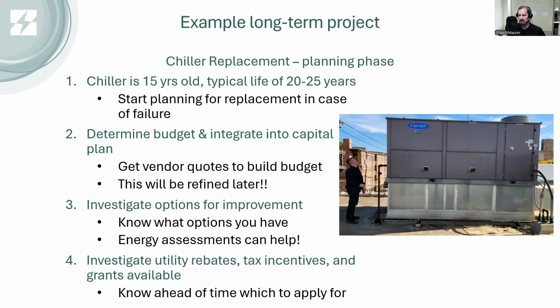Investigate the options for your improvement. With a chiller, you could replace it with an air-to-water heat pump system and get heating and cooling from the same piece of equipment, or just install a more efficient, smaller chiller unit. Energy assessments can really help narrow down the best option for you, with the best payback and economics. This is where you can tap into consultants through the utilities' assessment programs or engineering firms, who can help with life cycle costing and planning for new equipment.